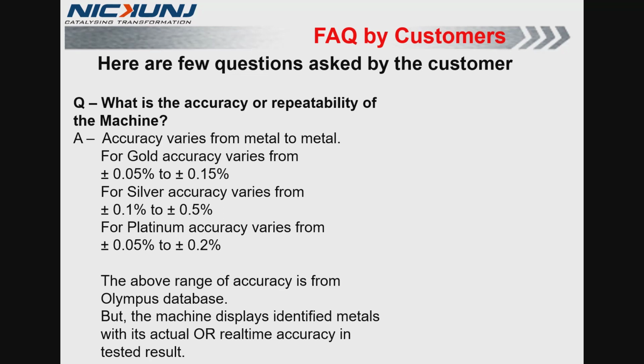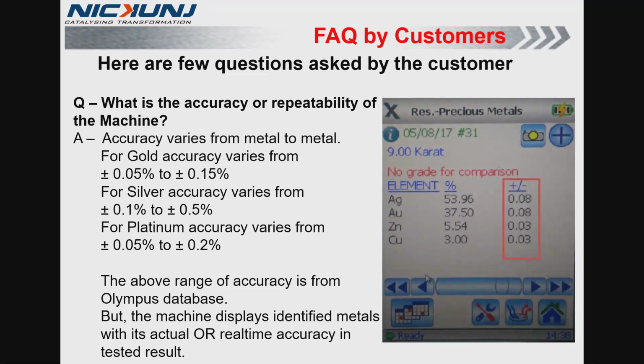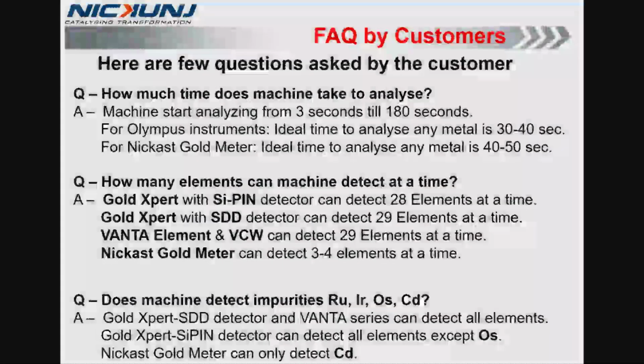Customer can ask you what is the accuracy or repeatability of the machine. Accuracy varies from metal to metal. For gold, accuracy varies from plus or minus 0.05% to 0.15%. For silver, accuracy varies from plus or minus 0.1% to 0.5%. For platinum, accuracy varies from plus or minus 0.05% to plus or minus 0.2%. The above range of accuracy is from Olympus database, but the machine displays identified metals within its actual or real-time accuracy in tested results.